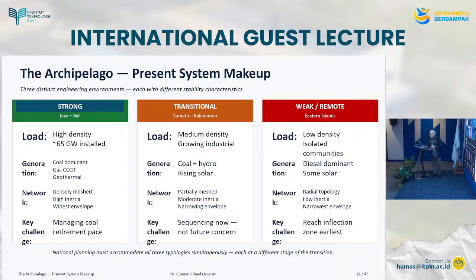A low inertia system is one where 1 to 3 diesel units provide all the inertia of the system, which in the outer islands is 1 to 2 seconds. Adding solar replaces synchronous generation and reduces the H further. So if it is 2, it's going to go down to 1. If it is 1, it's going to go down to 0.5. A trip of 1 diesel means a catastrophic H reduction, and it is not gradual, and there is no governor headroom for the system to pick up the frequency.